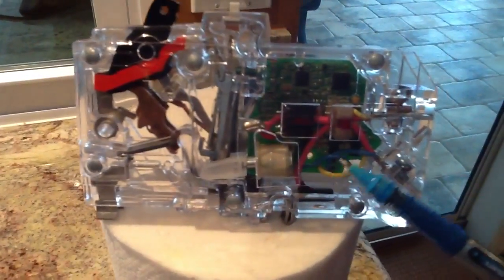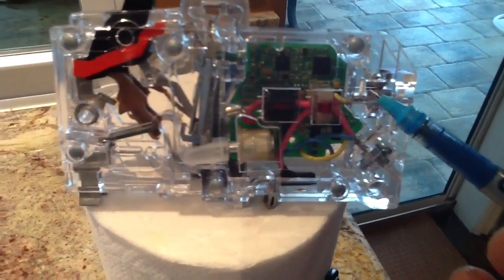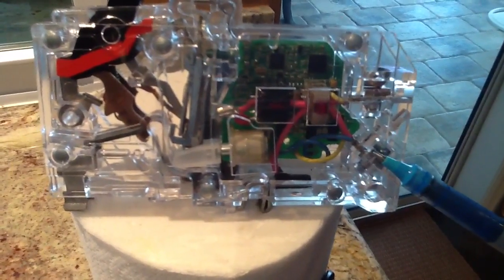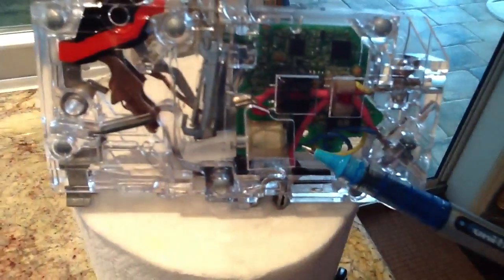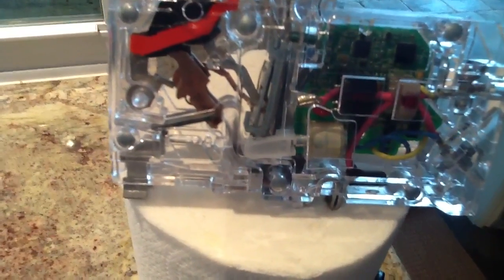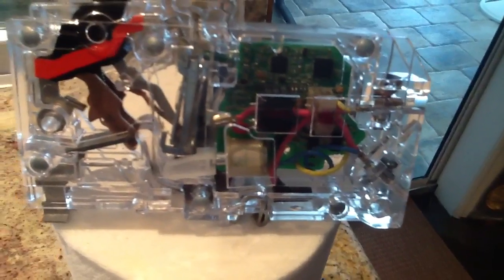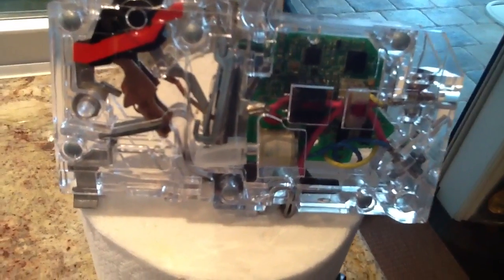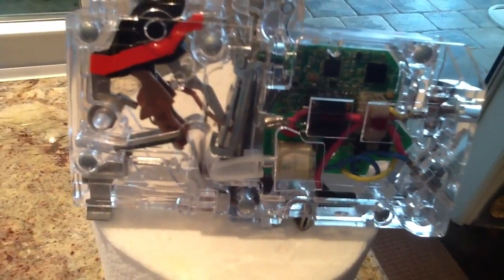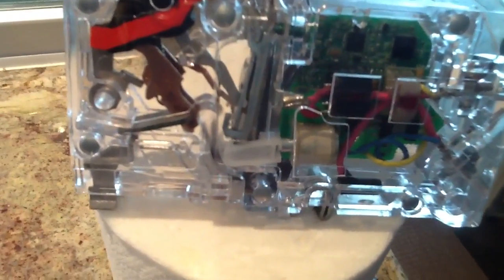The next thing I want to talk about is the amplifier, which is this device right here. If you notice the amplifier, you have a yellow wire that's tied to the dark screw, and a pink wire that's tied to the neutral screw. Those components actually go back again to the transformer. The amplifier is powered by the circuit itself — it's got the 110, 120 volt lead coming into it. It's a device so sensitive that it will let a balanced current load of 15 amps go through it, but it will detect a 5 milliamp — which is 5 thousandths of an amp — and that's what will trip the solenoid. The operation time of the solenoid is 1/40th of a second.